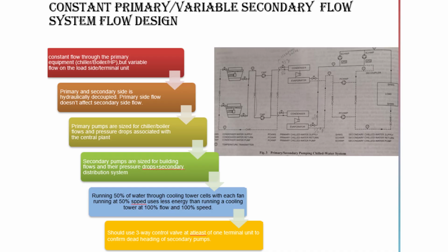In a constant primary and variable secondary flow system, the primary side maintains a constant flow through the chillers, boilers, or heat pumps, while the secondary side varies based on the building load. Let's look at how this system works. The primary and secondary loops are hydraulically decoupled by a common pipe or decoupler.